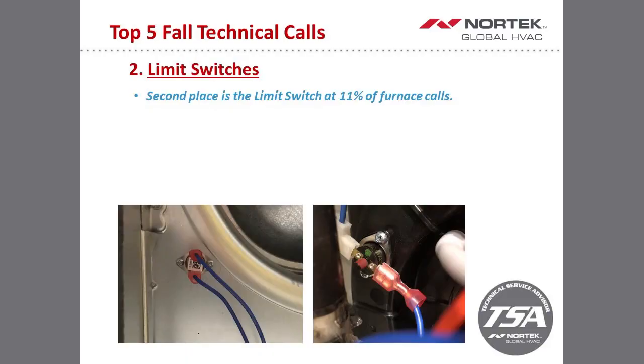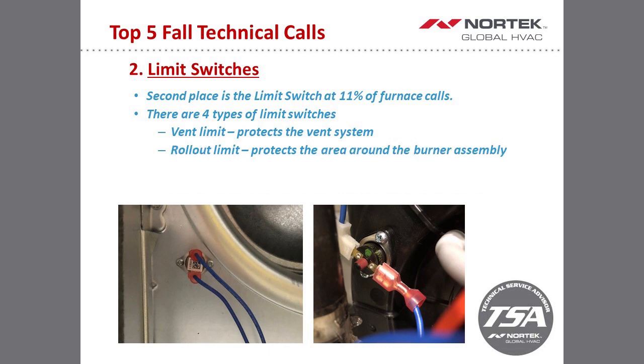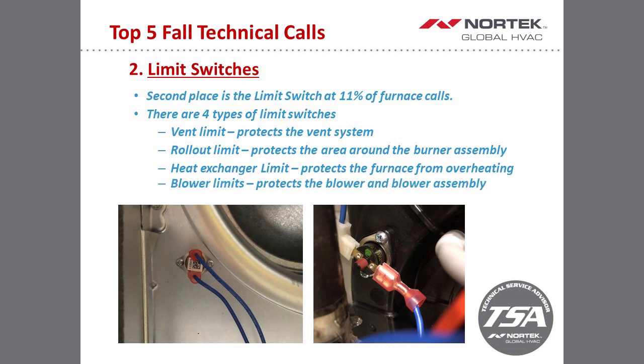But at 11%, this is another main topic that we get tons of calls on in the tech service in regards to limits. So there are 4 types of limit switches in a furnace. You'll have your vent limit, which will really only apply to the high efficiency side. So anything that's 80% will not have a vent limit, but your vent limit will be located on the inducer. All furnaces will have a rollout switch. They'll have your main air heat exchanger switch, and then every furnace as well will have blower limits. You will have a blower limit on either side of the blower housing. So just keep that in mind when troubleshooting. So you'll have 5 limits in a high efficiency furnace, and you'll have 4 limits in an 80% furnace.